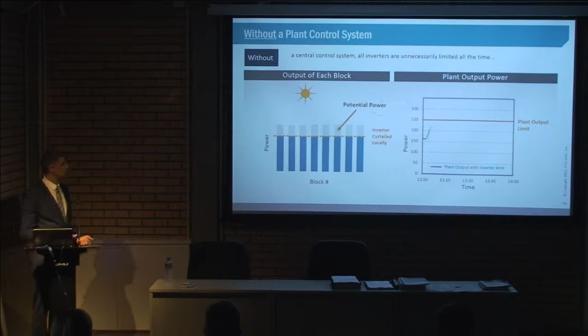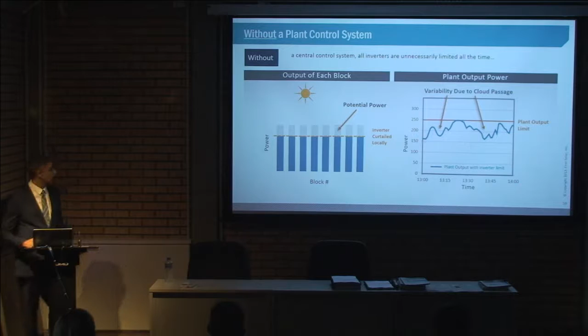On a sunny day it's fine, but clouds come in, and you lose some inverters or the power rate drops, which affects your energy output. You can see these valleys here due to cloud passage. This is your fixed setting, but this is your actual output, so all the space between the line and the curve is energy you weren't able to deliver.